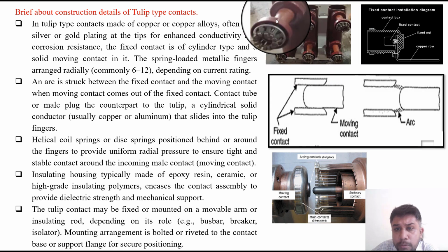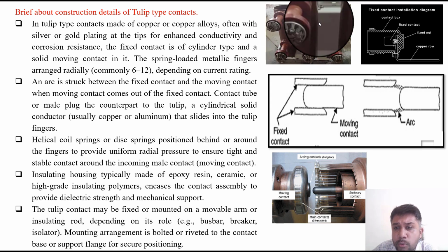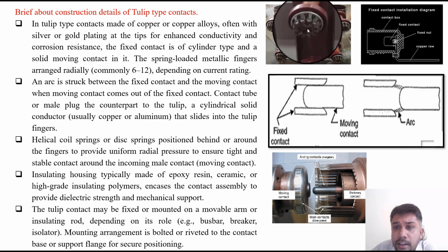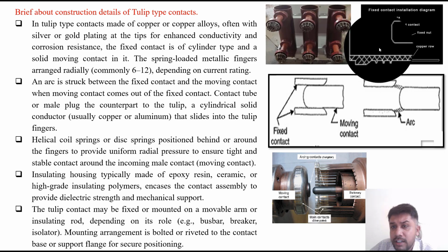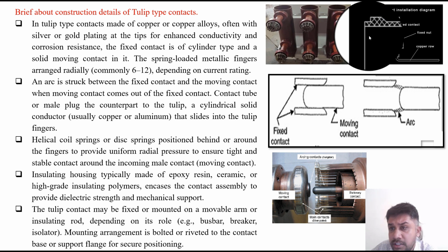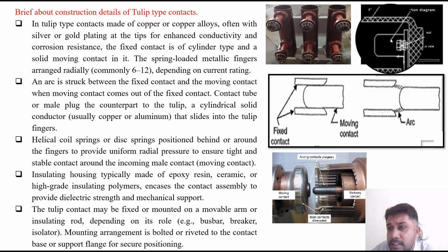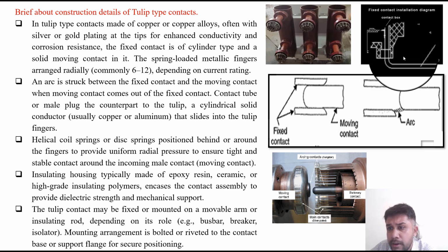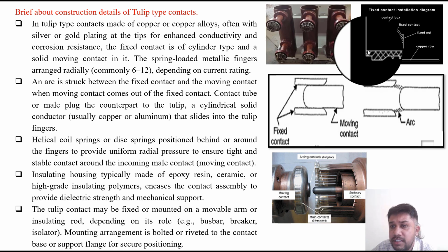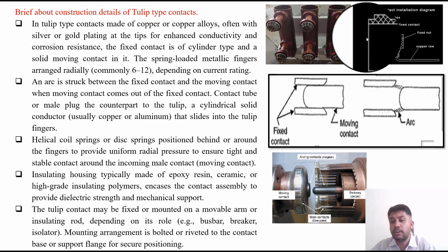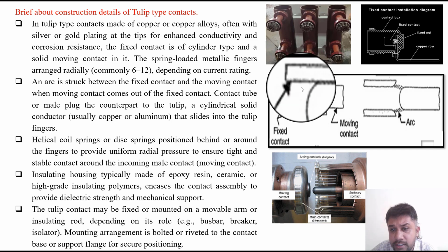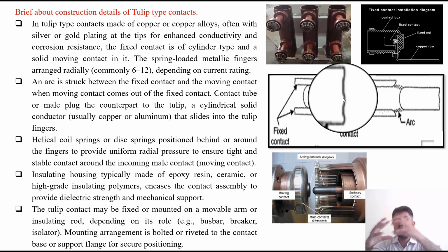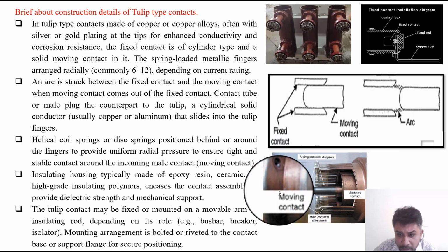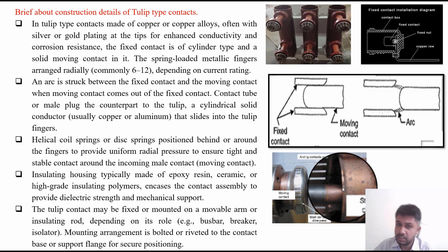This is generally used for the vacuum circuit breaker, 3-phase, like R, Y and B. These are the tulip fingers or the fixed contacts. Their assembly you can easily understand with the diagram. This is the fixed contact. These are the fixed nuts and this is the copper rod, that is the connection of the contact. This is the contact box where the male contact is going to be connected like this. So these are fixed contacts or tulip fingers, and the moving contact is inserted inside it. The same assembly you can visualize in this figure as well. So this is how tulip contacts are constructed and they can be utilized in the breaker.